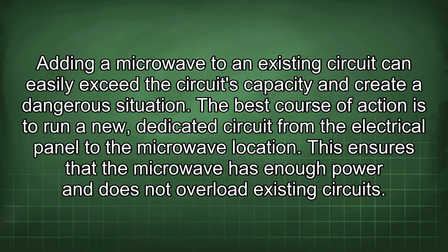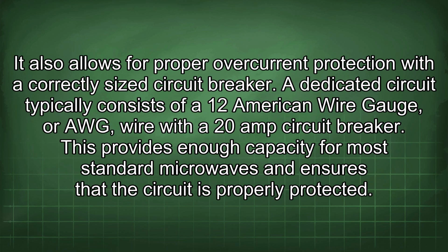The best course of action is to run a new, dedicated circuit from the electrical panel to the microwave location. This ensures that the microwave has enough power and does not overload existing circuits. It also allows for proper overcurrent protection with a correctly sized circuit breaker. A dedicated circuit typically consists of a 12 AWG wire with a 20 amp circuit breaker. This provides enough capacity for most standard microwaves and ensures that the circuit is properly protected.